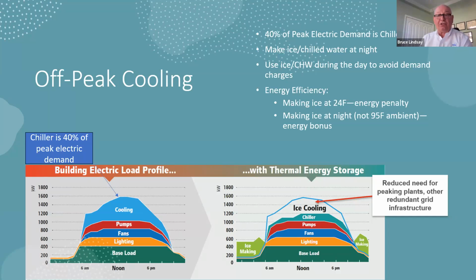There is the on-peak energy charge, and more importantly, there's the demand charge, or $13 per kW per month. And it's significant. The intent is, instead of making ice or providing cooling during the day, let's make ice at night and turn the chillers off during the day. And it's huge dollar savings. It doesn't really save energy. Making the ice, you're operating at a lower temperature, so there's a slight energy penalty. However, you're making ice at night. The ambient temperatures are much lower, so it's basically a wash. Next slide.